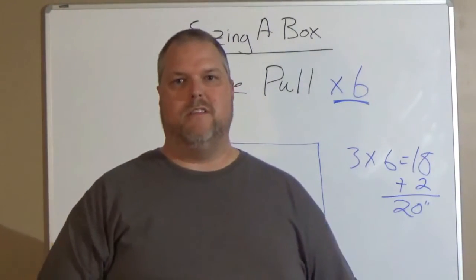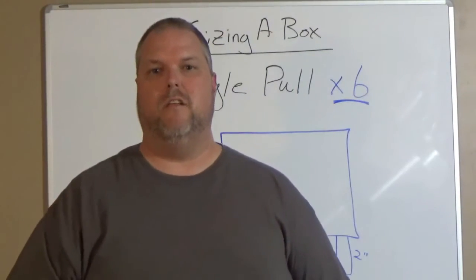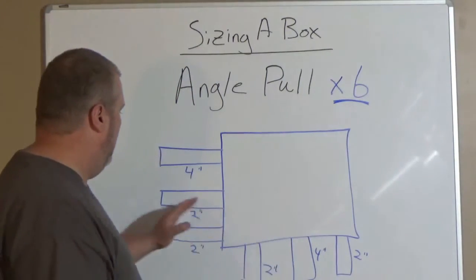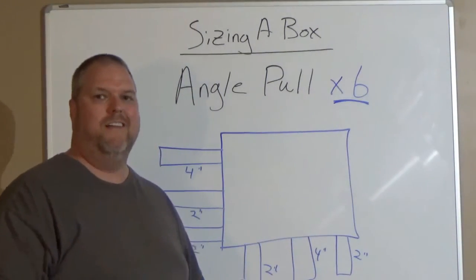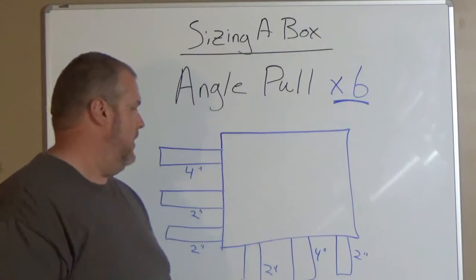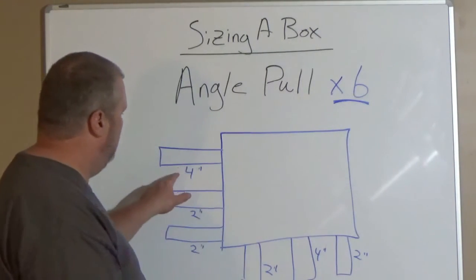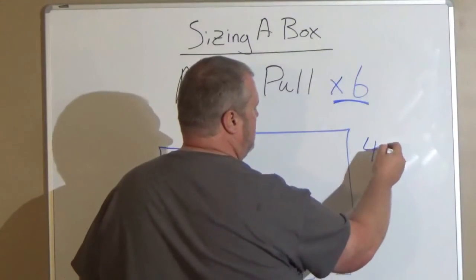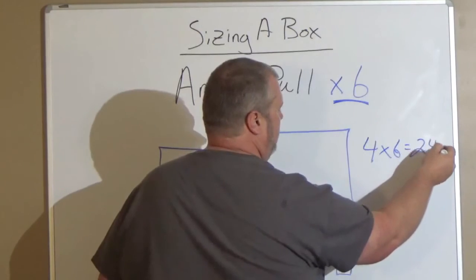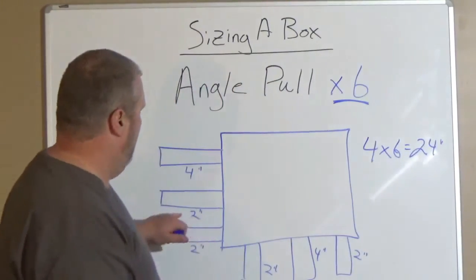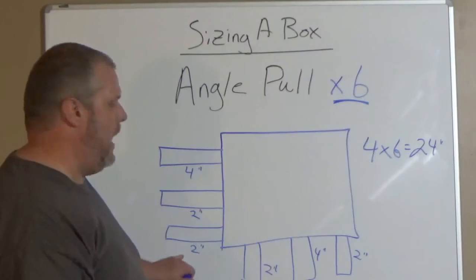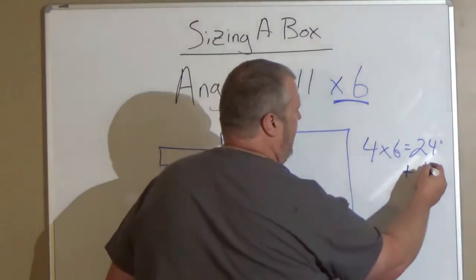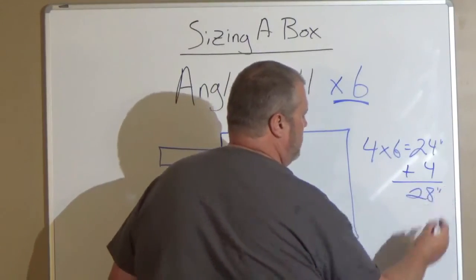Let's do one more example. This example is we have three conduits. So three conduits, we do the same thing. I have a 4-inch conduit. That is my largest conduit on both sides, but we're going to do one side right now. So I'm going to take the 4 and I'm going to multiply that by 6. That's going to give me 24 inches. I have two 2-inch conduits. I'm going to add them together, which will give me 4 inches. I'm going to add the 4 to this, and it's going to give me a 28-inch box.